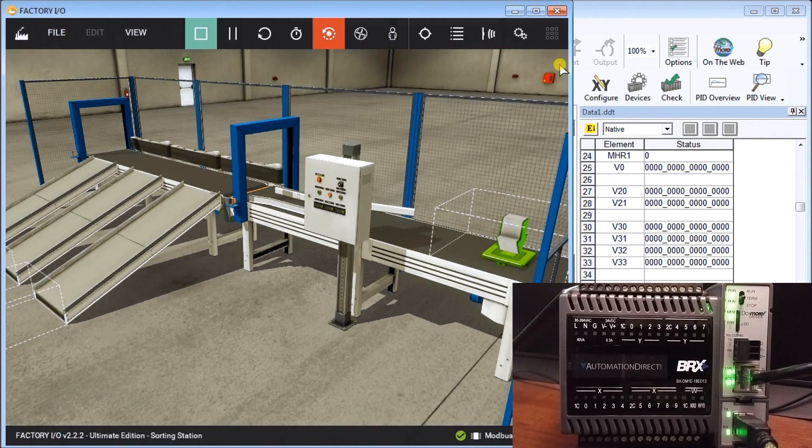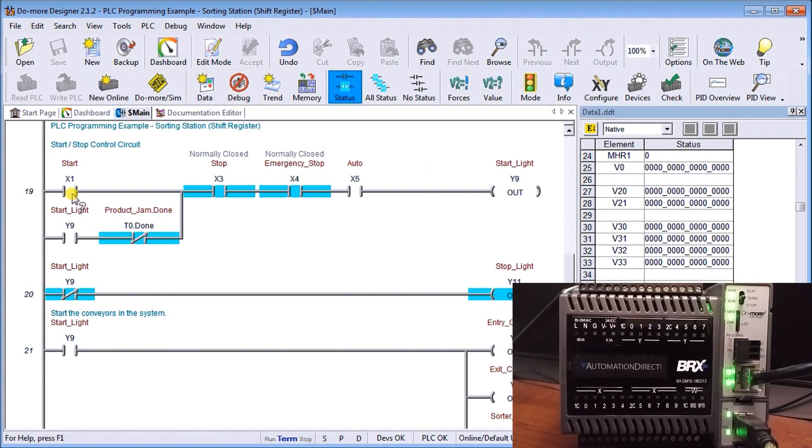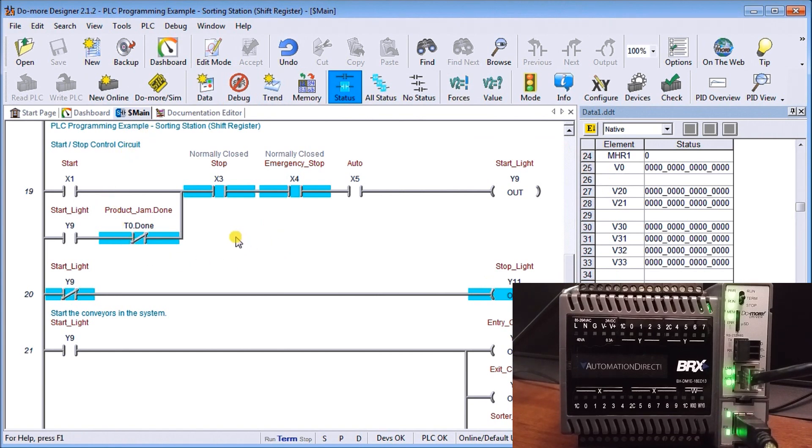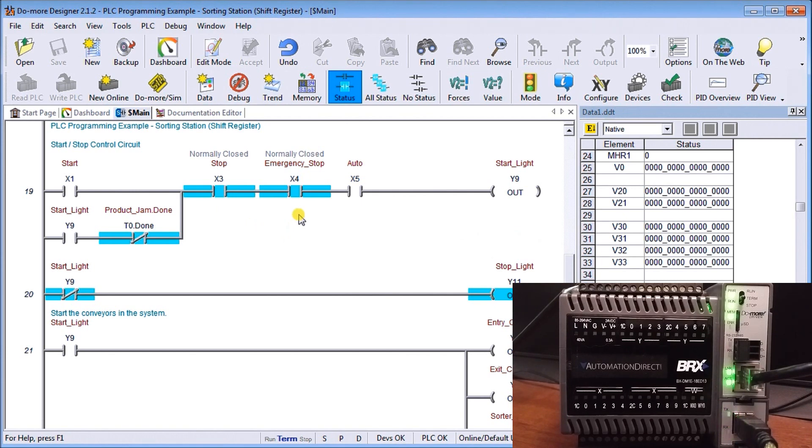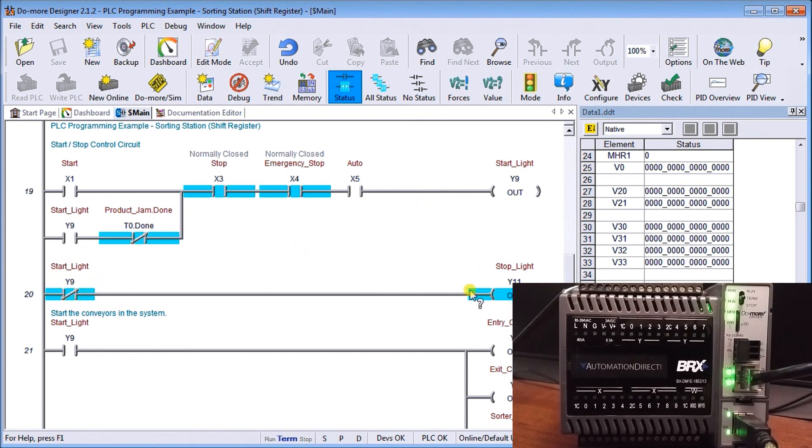If we look back at our logic, we start off with a start and we use our latching circuit. We go through normally closed, we go through emergency stop which are normally closed wired, and it has to be in auto. It'll start, put the start light on, and as long as we don't have any jams of our product on our conveyor, then it will start. If the start light is on, the stop is off, and vice versa.